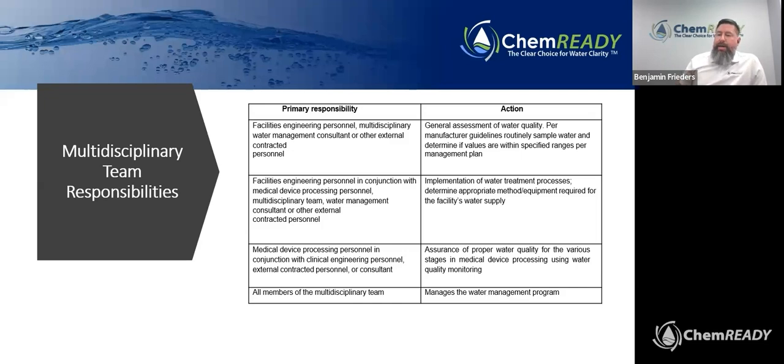The city water supply can vary vastly in being compliant with the utility water standards. Also includes medical device processing personnel in conjunction with clinical engineering or external consultants again. Their actions and responsibilities include assurance of proper water quality for the various stages in the medical device processing.